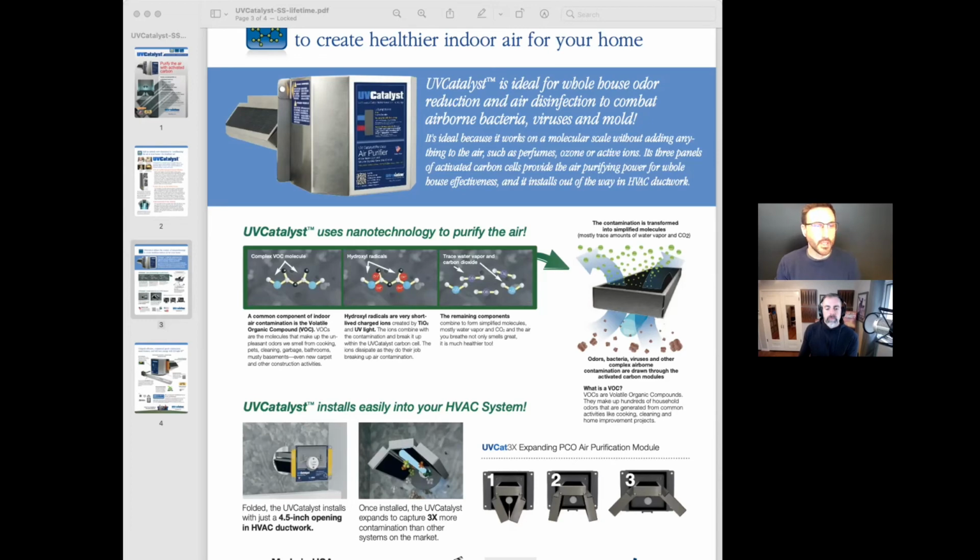And just to let everybody know too, the Orion, you don't need to replace the Orion. It does need to be cleaned every once in a while. It does not emit any ozone. And then all the bulbs that we are talking about today for the UVC, a lot of people ask, how often do you need to replace those? They do have a 2-year lamp life on each one of the bulbs we were speaking with about today. So every year you should be getting your HVAC system looked at anyway, and then every 2 years you would replace the bulbs on these as well.